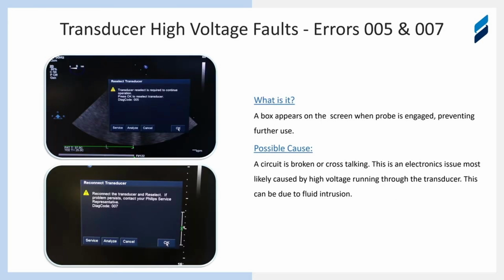Here we have just some pretty catastrophic error codes, specifically 005 and 007. And what this typically means is that there is just a circuit that carries high voltage in this probe. They all don't carry high voltage, but some of them do. And that is shorting to something else. It could be shorting to another high voltage circuit, could be shorting to ground, could be shorting to anything that's inside the transducer to another wire. So just a variety of things that can happen. And the short could be just chafing of the wires together over time, or it could even be some sort of fluid intrusion where one drop of fluid will actually short dozens and dozens of wires together. And if they're not properly sealed, can cause an instantaneous short and cause some pretty serious damage.